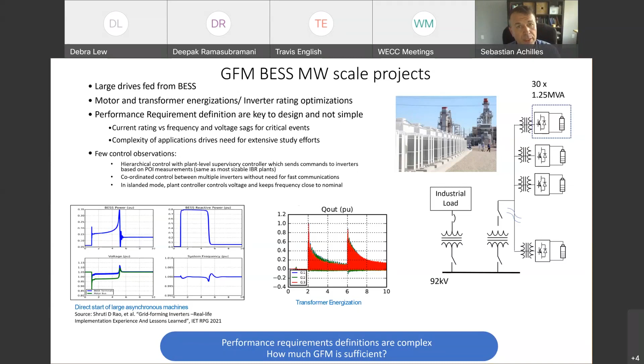Energization of transformers - in general we did soft energizations, as Julia mentioned, but we also looked into direct start of transformers as part of the design. In general, these grid forming requirements were very demanding. We had to be able to do all of these things with these little inverters. Now, you could argue these requirements were too much for what is needed in an interconnected system, so the definition of these requirements is actually key to defining the functions you have and how to deal with the limitations of equipment.